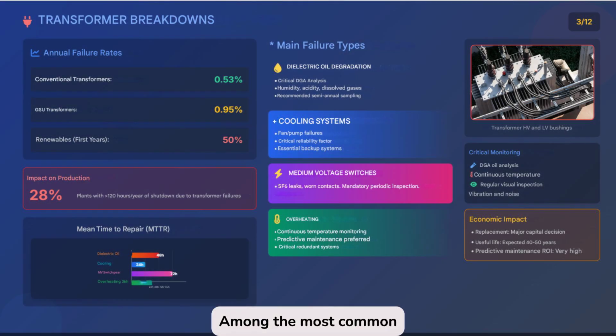Among the most common causes are dielectric oil degradation, detectable through dissolved gas analysis, DGA, cooling system failures, which are particularly serious in hot climates, wear or leaks in medium voltage switchgear, which require periodic inspection, and progressive overheating, which can go unnoticed until it's too late. Therefore, anticipation is essential. A monitoring strategy that combines DGA, temperature sensors, visual inspections, and vibration analysis drastically reduces the risk of critical failures. It also enables more informed technical and economic decisions.